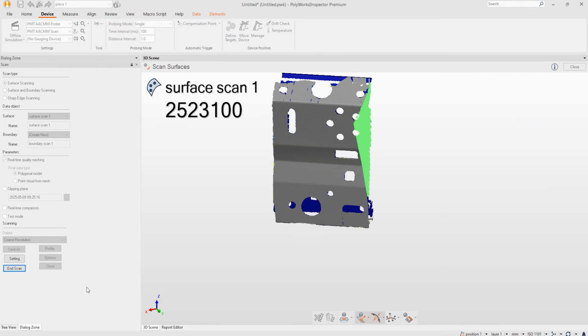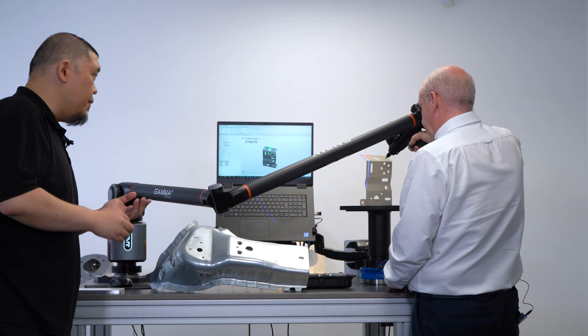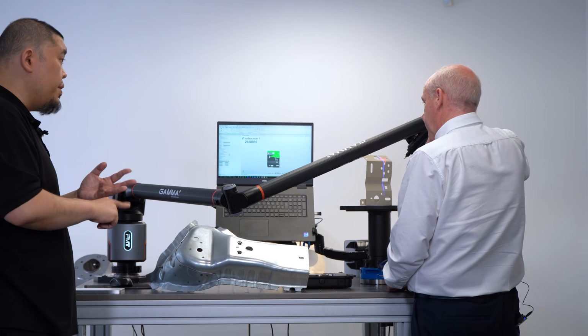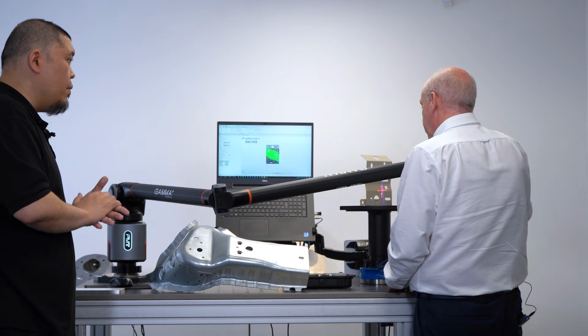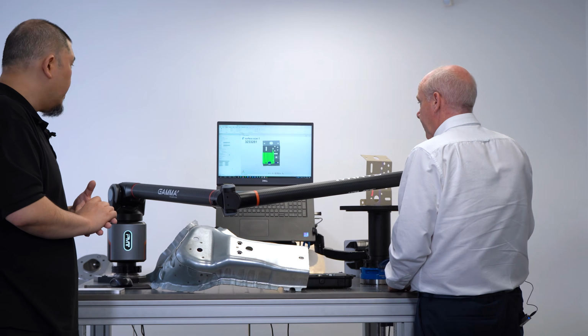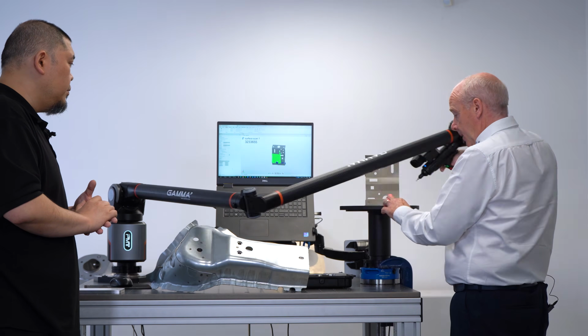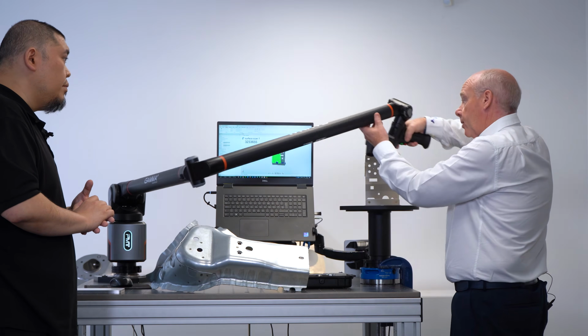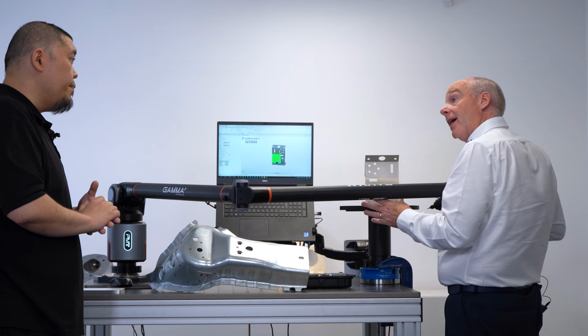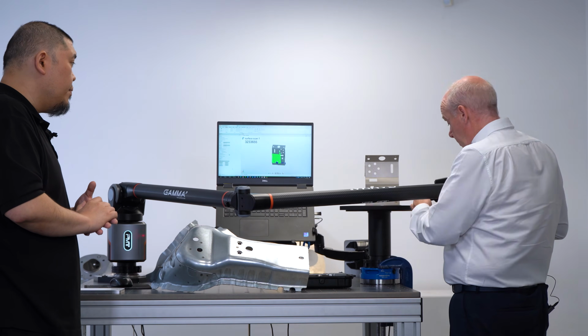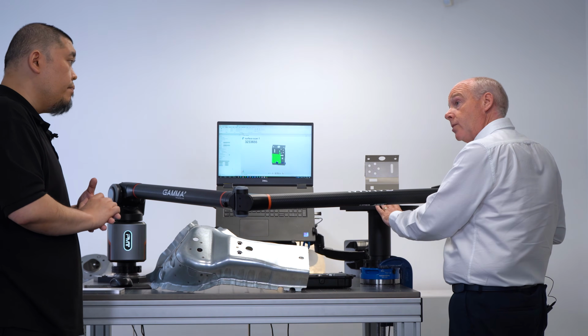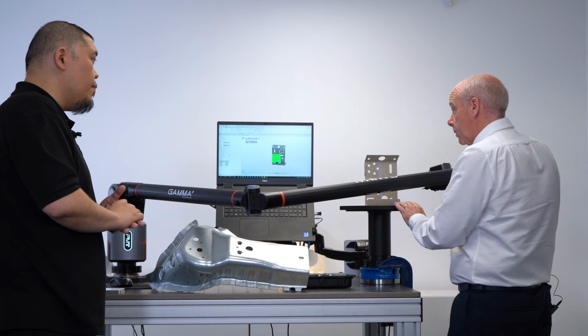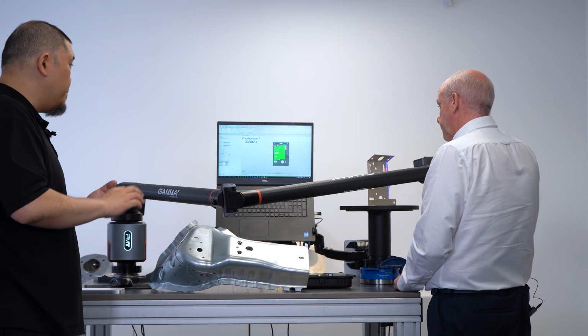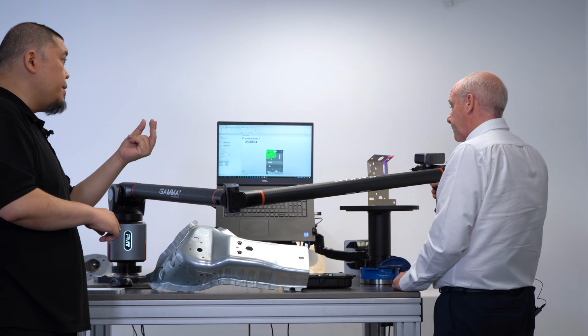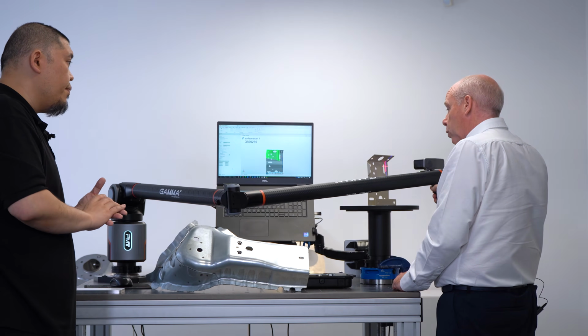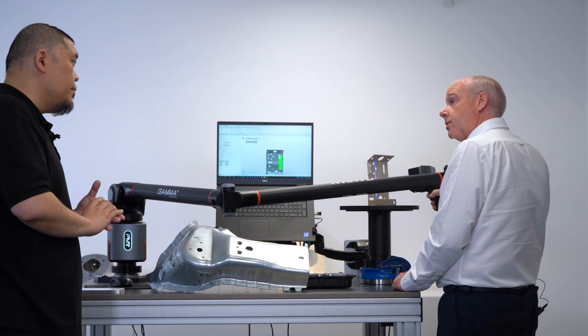And in terms of the calibration process with the arm, obviously we're calibrating the probe, the scanner, the turntable. Can you give a bit more information on how? Basically the turntable itself has a point in it. All we do is put the arm in the point and do a full 360 rotation. And that calibrates. So it then knows where the arm is, it knows where the probe is, it knows where the scanner is, and it knows where the rotary table is relative to the arm's coordinate system. And in terms of calibrating the probe itself, it's just the typical nest that you rest into? Yes, that would be on the old ones. The kinetic ones come calibrated, so they should be plug and play.